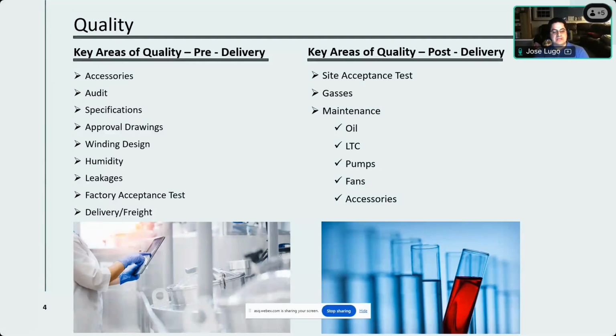There are pumps in some of these transformers. The really big ones have pumps because you want to keep the physical size of the transformer fairly small, and sometimes that requires pumps. Those need maintenance too, which means you have to de-energize the entire transformer. These are usually really big units, so it's a big deal to maintain them.